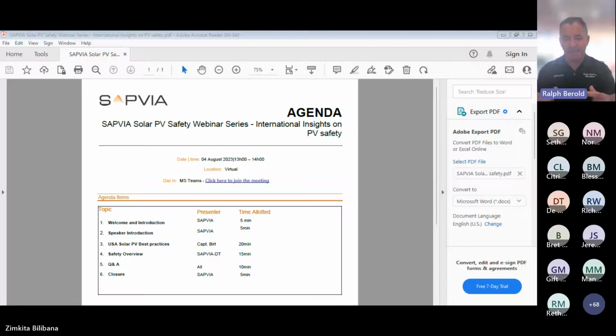So we said, okay, coming down from the roof that was causing all the fires, how do we control the arc fault, the heat, the fire down at the inverter? Where's the inverter? Usually next to the battery. So we said, if we eliminate the high voltage DC and the weak points in the inverter, the MC4 connectors, we're making a safer environment so there isn't a fire event that heats that battery up. So what we're looking at here is a fundamental change in architecture. I'm kind of cheating because we started code in 2012. We're at 2023. We have rapid shutdown. We have many, many fire safety codes that match an AC architecture, and we did it for a reason.